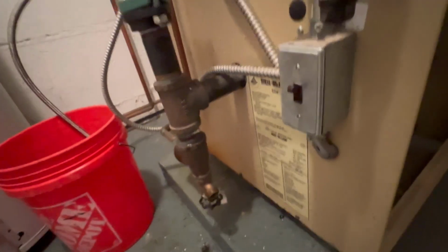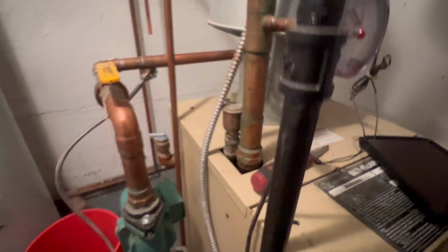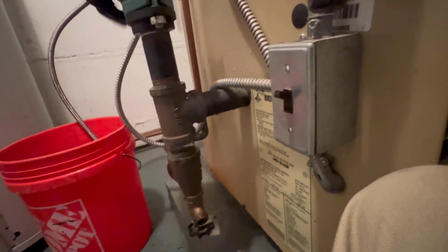What kind is this now? This is a Taco 0010 with an internal flow check. Remember that flow check device that I mentioned to you before? Yeah, that mine didn't have. Yes, it didn't have. In most cases, when the pump is not running, people are complaining that they still have heat from natural, gravitational flow. This has got the internal flow check in there, and that prevents that.